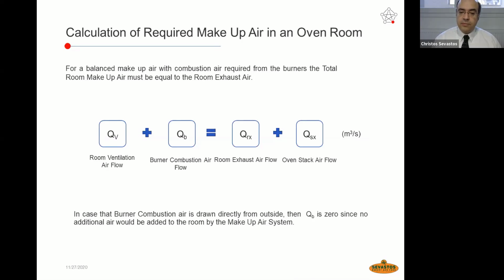In case that burner combustion air is drawn directly from outside, the QB, which is the burner combustion airflow, could be zero. This is rarely happening, of course, in tunnel oven installations, but whenever we have a dedicated airflow being introduced in the zones, in the burners of a tunnel oven, then this could be taken as a zero.